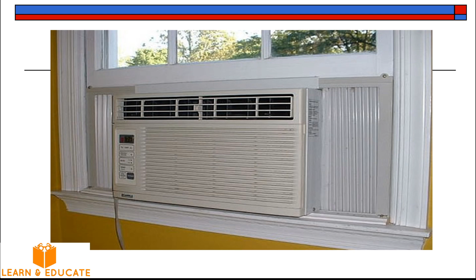It has two different components, the cooling unit and the condensing unit. The cooling unit comprises the evaporator and the fan. The condensing unit comprises the condenser and compressor. So the noise-making component, the compressor, is placed outside, as well as the heat rejection component, the condenser. These two are assembled as a single unit and placed outside, and the cooling unit and condensing unit are connected through a pipeline.